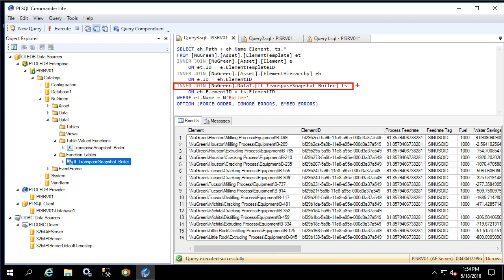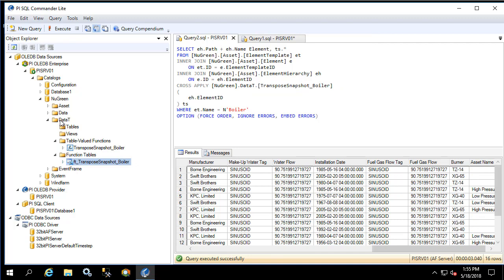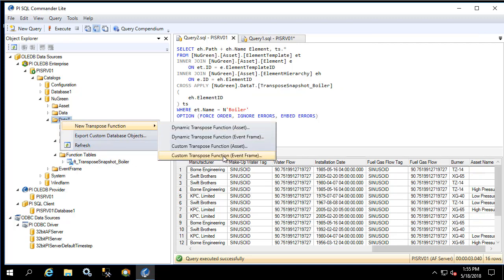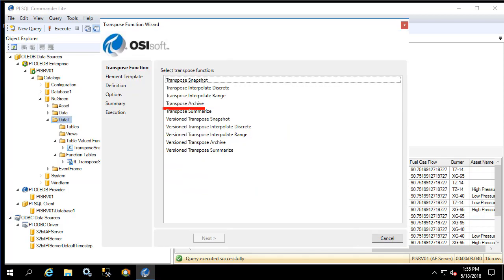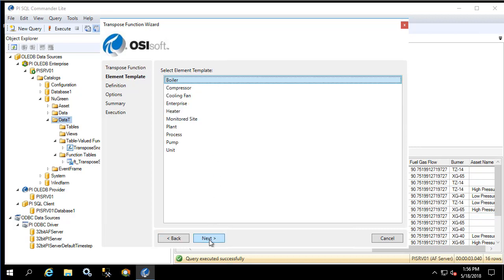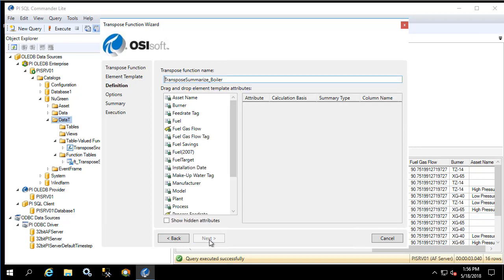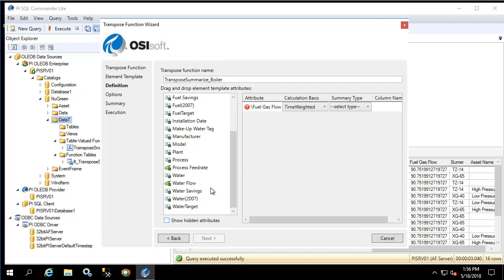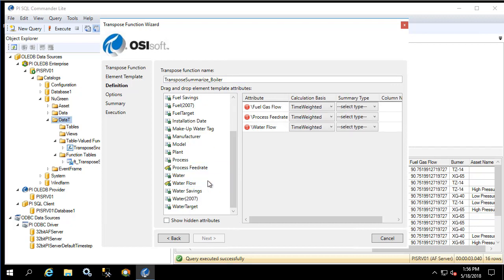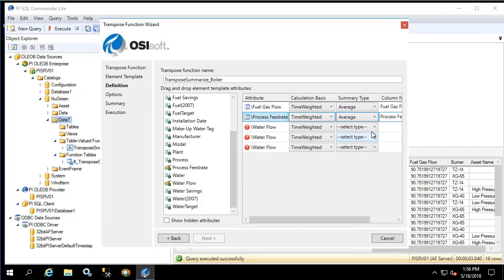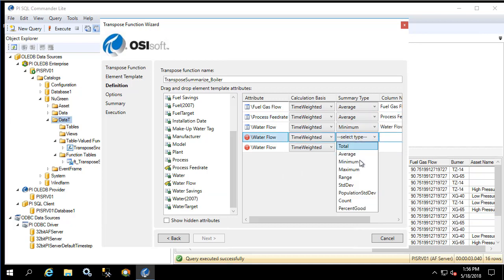Next let's create a custom transpose function for the same template so that we can show some summary values. Let's right-click on data T again, new transpose function, custom transpose function. Here we'll select transpose summarize because we want to obtain summary values. We'll select the boiler template again and drag in the attributes we would like: fuel gas flow, process feed rate, and water flow. Let's obtain the average for fuel gas flow as well as process feed rate, and the min, max, and standard deviation of water flow.